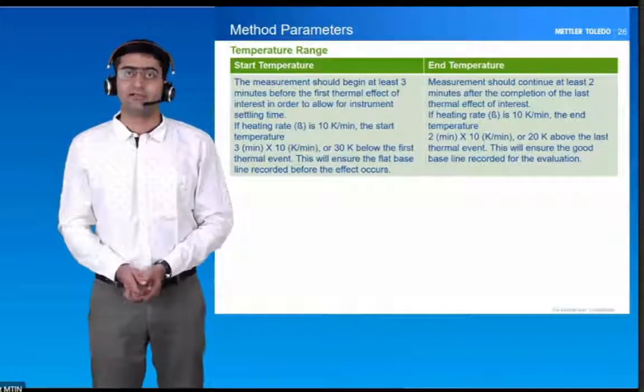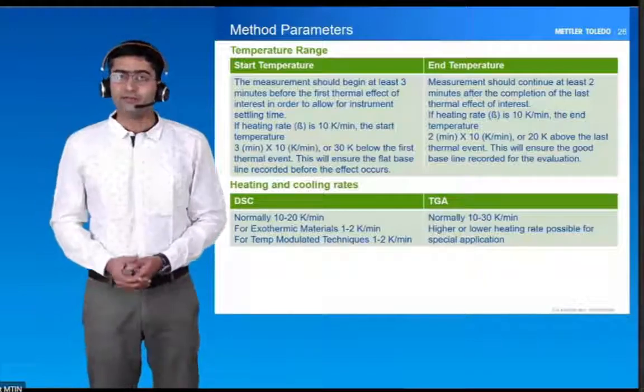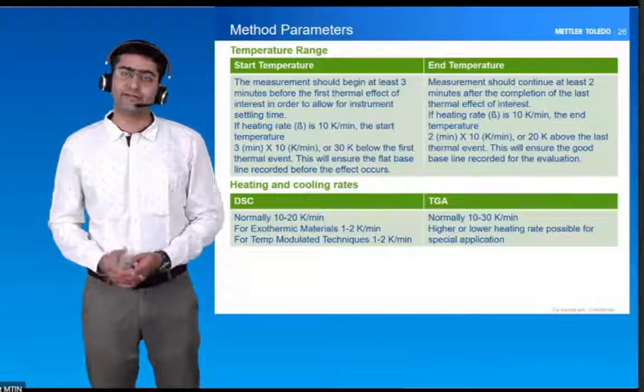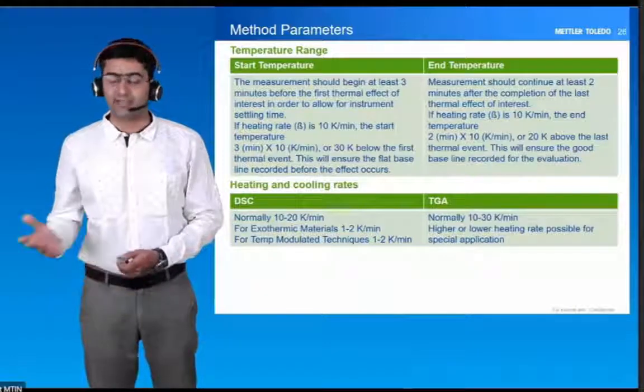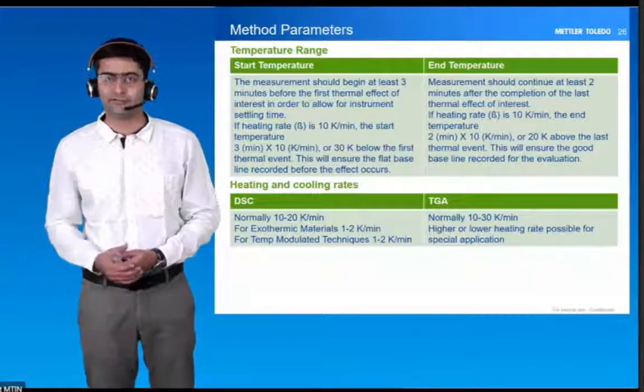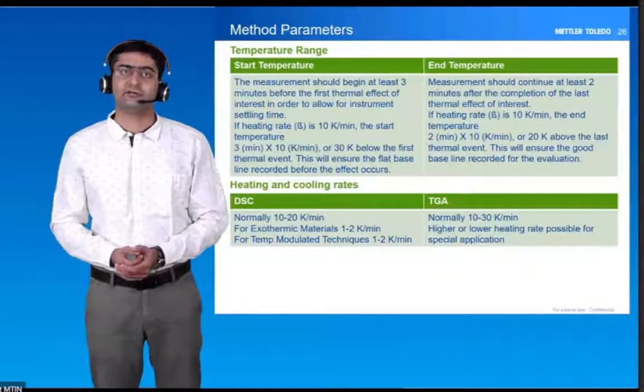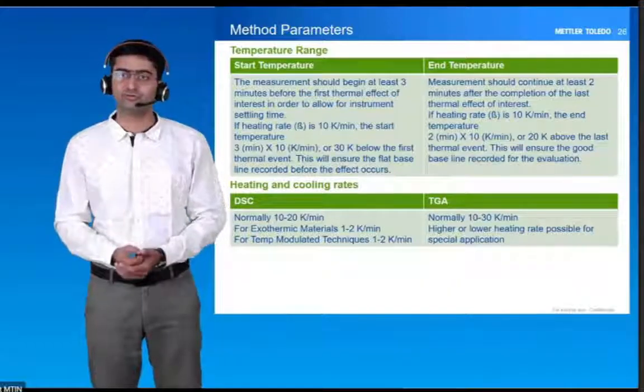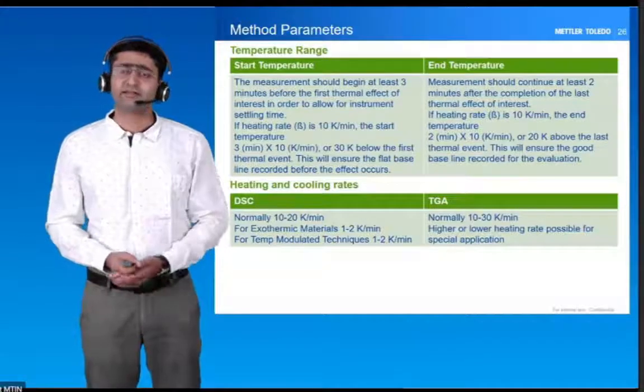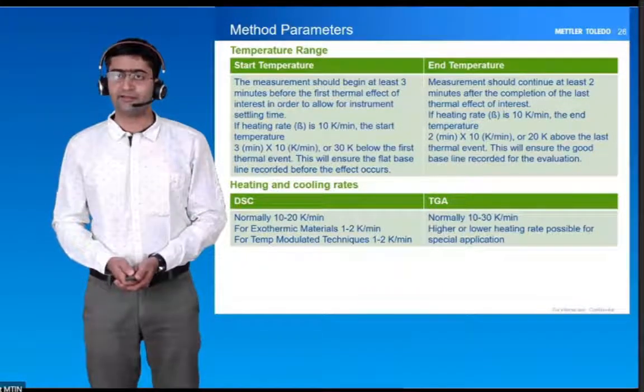That should be the temperature range. Regarding cooling rate — typically we use 10 to 20 Kelvin per minute heating rate in DSC and TGA; we can go up to 30 Kelvin per minute also. If the sample is exothermic, restrict the heating rate to 1 to 2 Kelvin per minute. If you are using a modulated DSC technique, then you will always have a 1 or 2 degree Celsius heating rate.